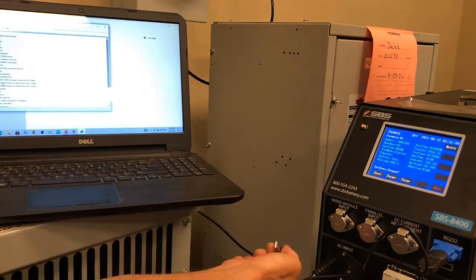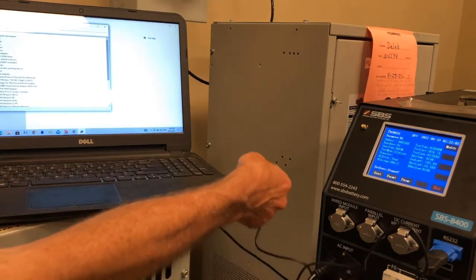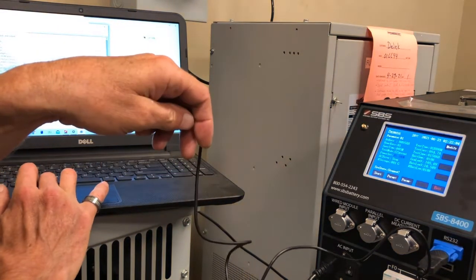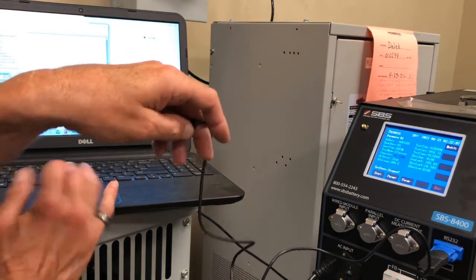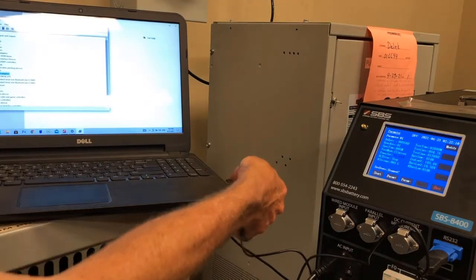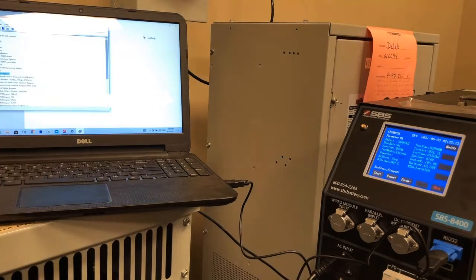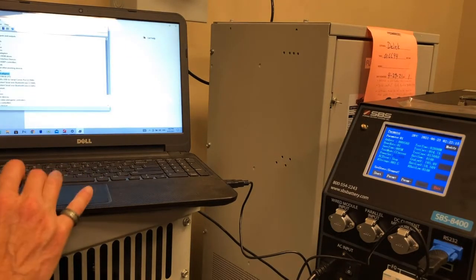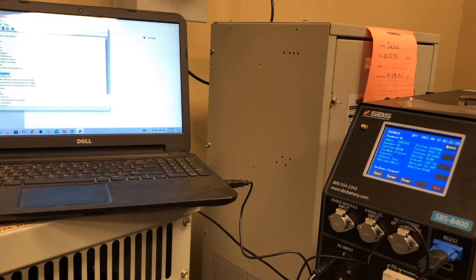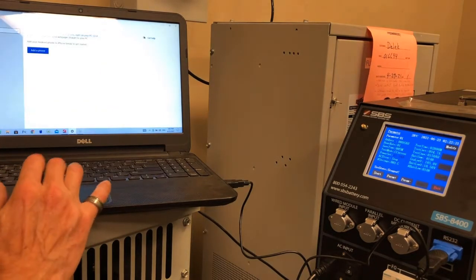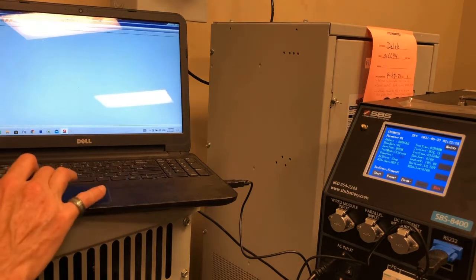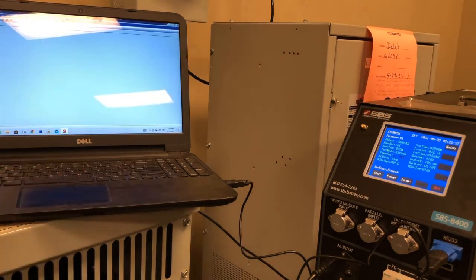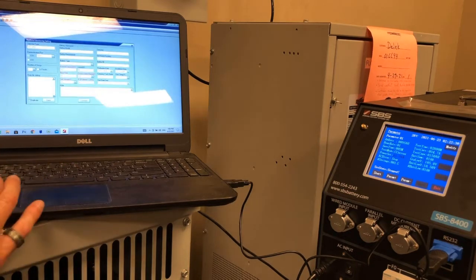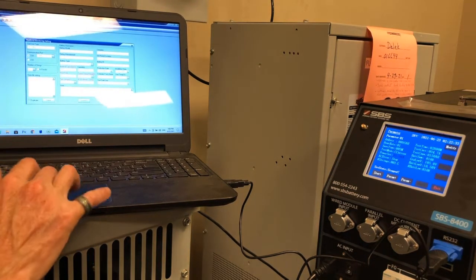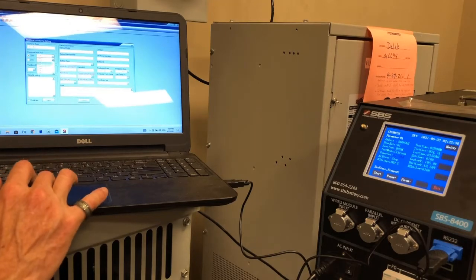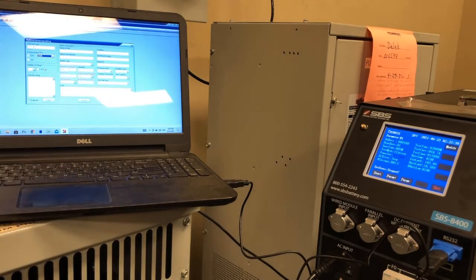The way you can check, disconnect it. It goes away. Right. So now if I look at that COM ports again, that COM 6 is going to be missing. So when I plug my USB back in, you hear it work, do its thing. COM 6. So I know I'm on COM port 6. So in the software, I click real-time monitoring. I click connect. Type a unit, SBS-8400. I'm on COM port 6. So I need to put that in there.